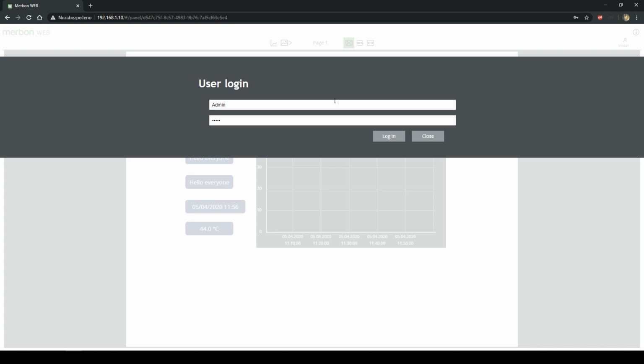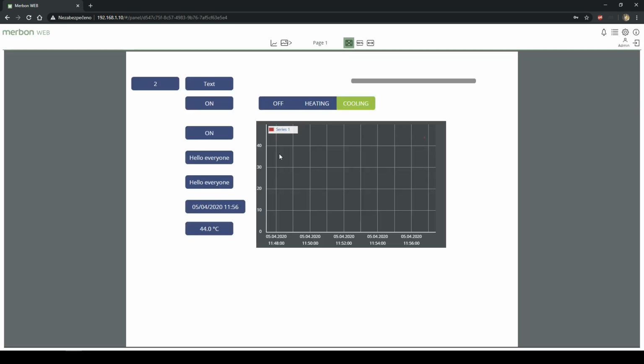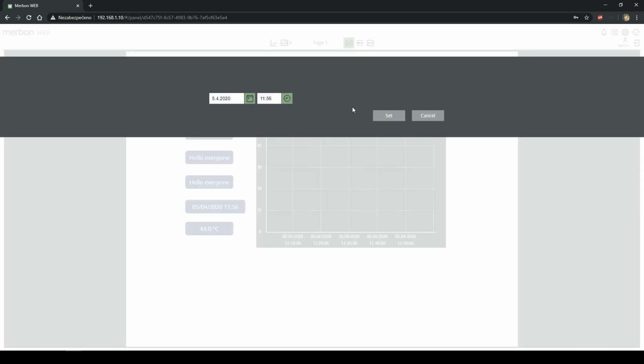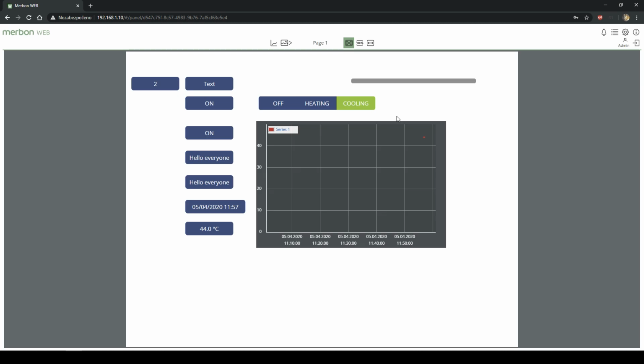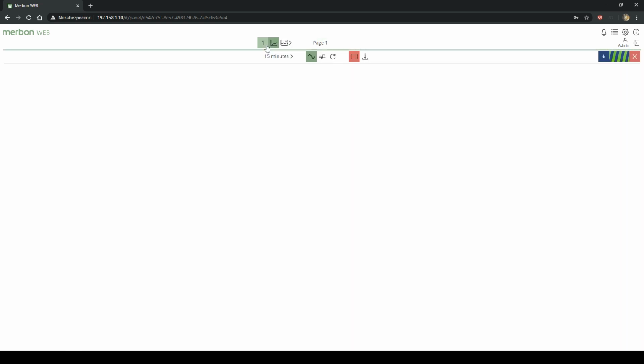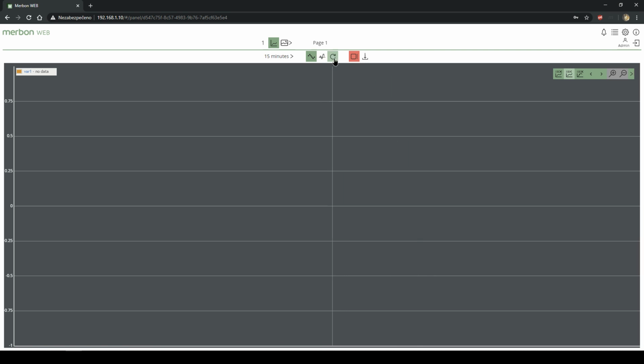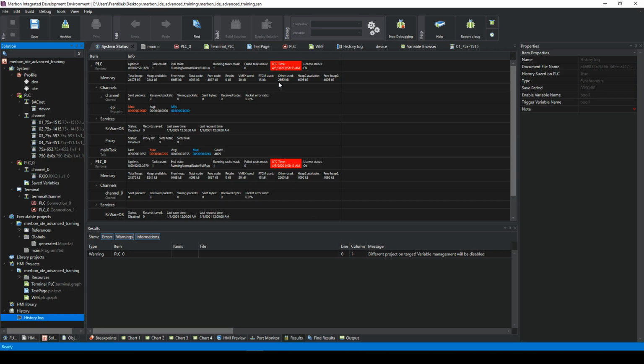Okay, I will just try one last thing, because the problem here is that the time is not synchronized. You see that there is a change here, so maybe that is why the history is not showing. So I will just change the time of the PLC.